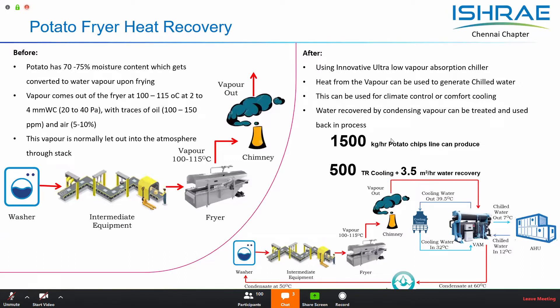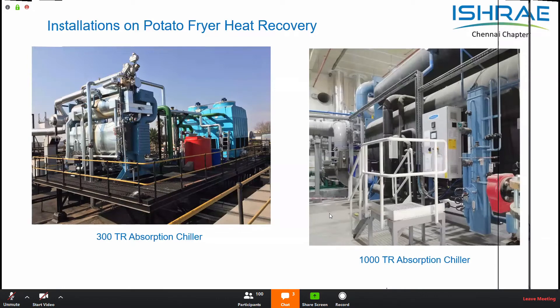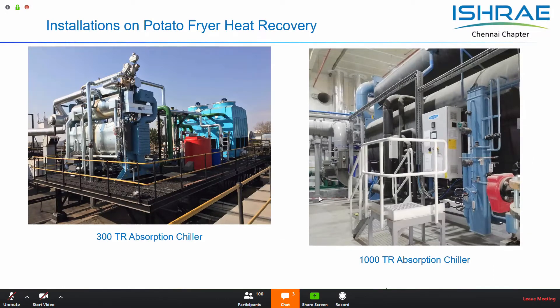This process also generates distilled water, which can be used as makeup water for cleaning potatoes or for cooling towers, making it a very sustainable solution. It helps reduce the carbon footprint and enables a zero-discharge kind of application. To give a brief illustration: for 1,500 kg of chips produced, the potential of recovery is nearly 500 tons of cooling and 3.5 cubic meters per hour of water — a huge saving for the industry. Such installations have been operational for many years and are available in various capacities in heat recovery applications.